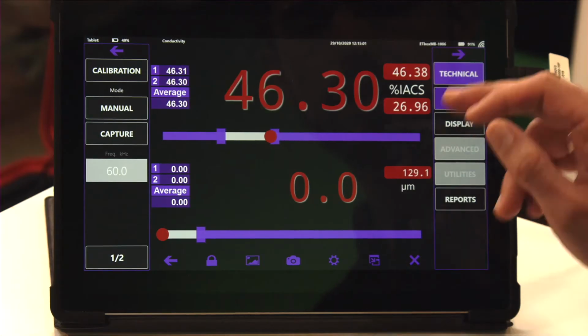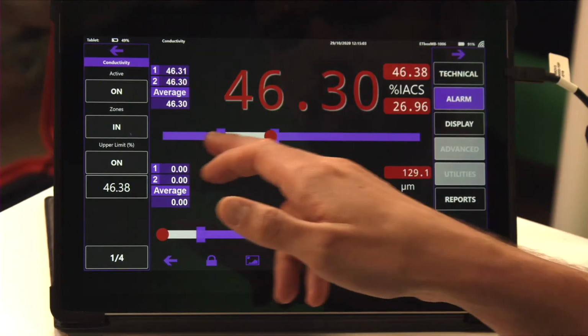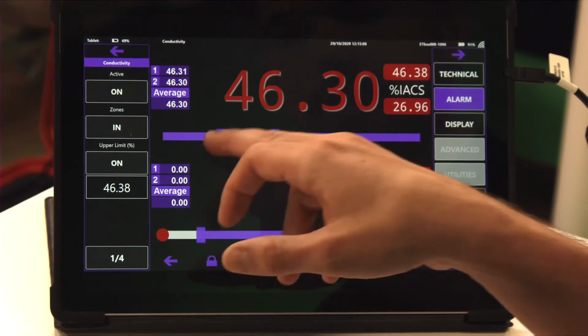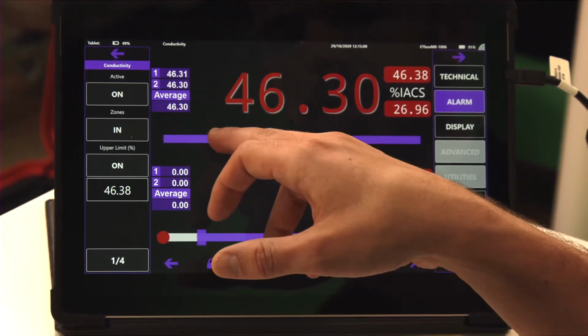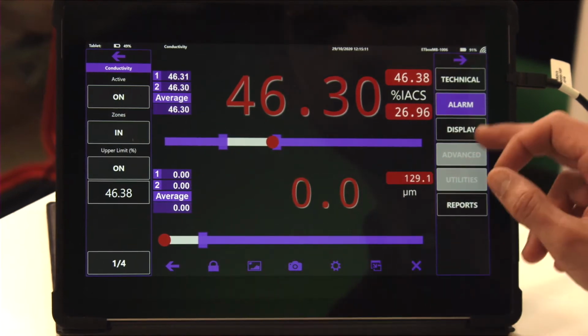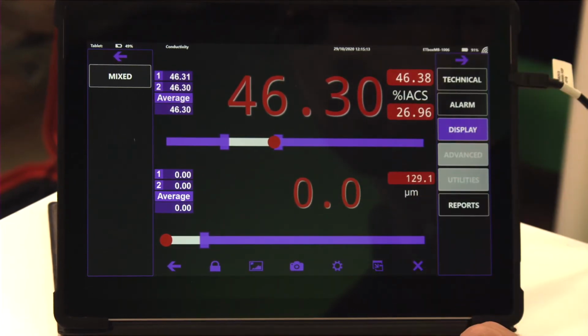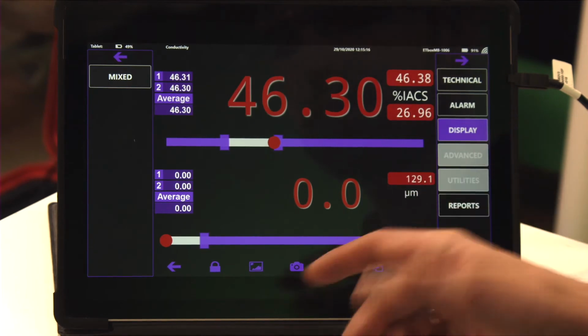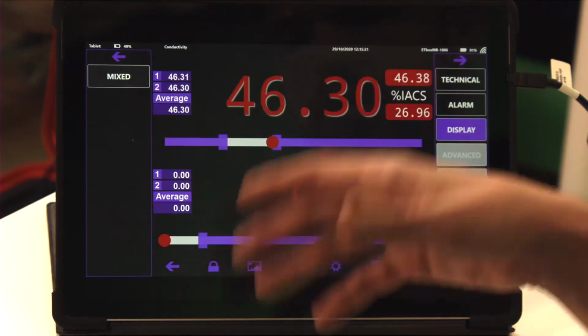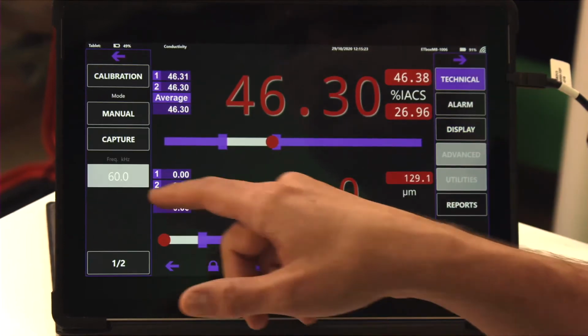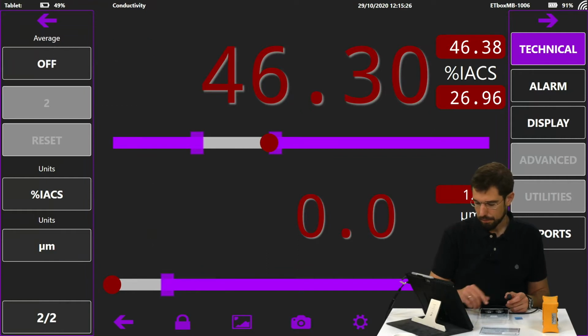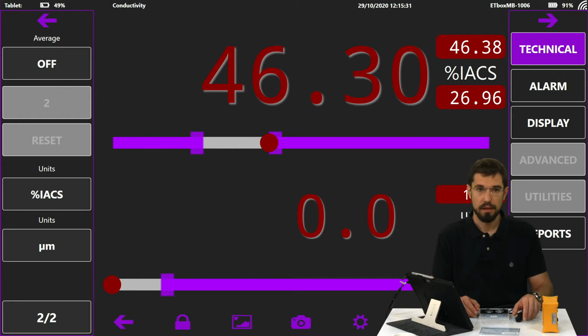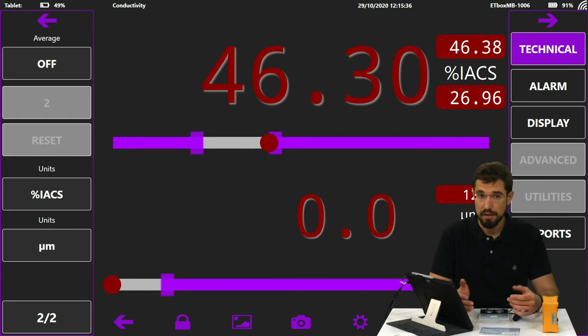On the other side, we also have an alarm set up. In this case, they've already activated, and we can see that the alarms go off when they're out of range. We also have the opportunity to change the display, but here we can only change between conductivity, thickness, or see both measurements. We have the chance to generate reports as well, but we'll see that later. This would be a general example of how to perform a combined inspection of conductivity and thickness.